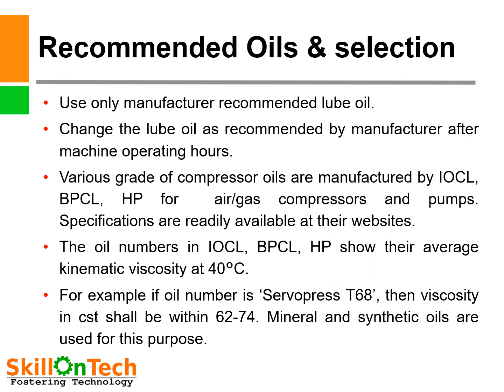For recommended oils and selection, use only the manufacturer-recommended lube oil for your pumps and compressors, and change the lube oil as recommended by the manufacturer after the specified operating hours. Various grades of compressor oils are manufactured by IOCL, BPCL, and HP for air, gas compressors and pumps. Specifications are available at their websites. The oil numbers show average kinematic viscosity at 40 degrees centigrade; for example, Servo Press T68 oil has a viscosity in CST within the range of 62 to 74. Both mineral and synthetic oils are used for lubrication of bearings.